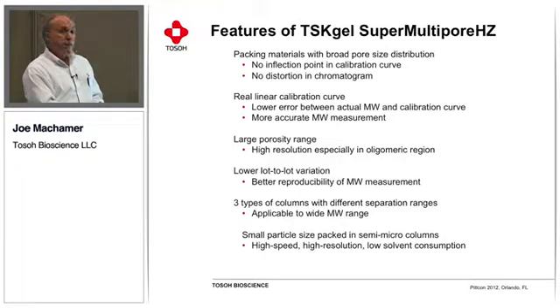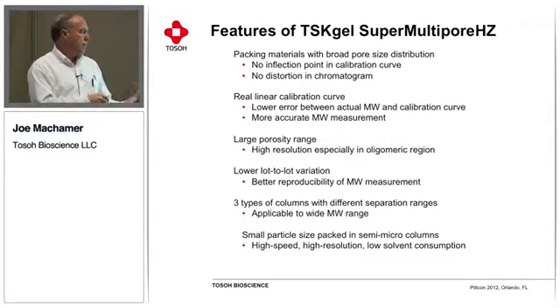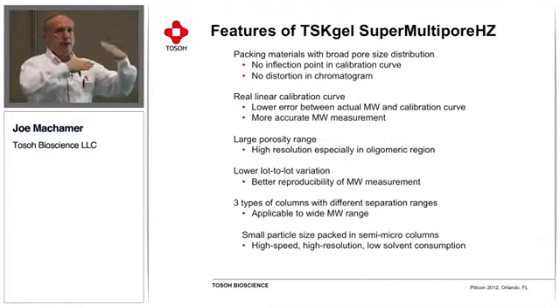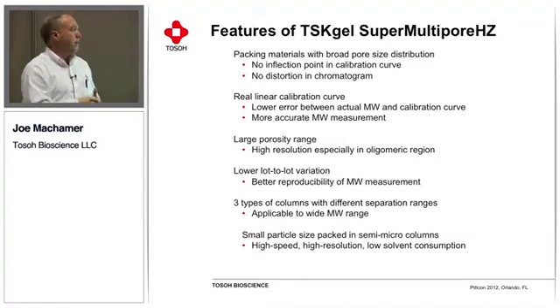The large porosity range gives you high resolution in the oligomeric region. And also because of the concept here, there's less lot-to-lot variation because we're not having to try to match different batches of beads to keep the calibration curves overlaying in a linear fashion. And also small particle size, which is providing for high speed and high resolution with low solvent consumption.